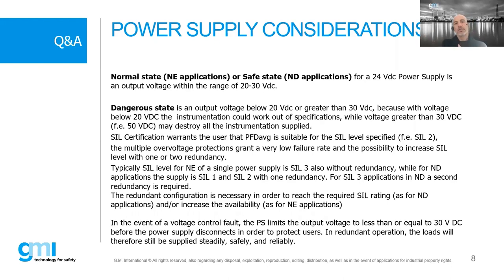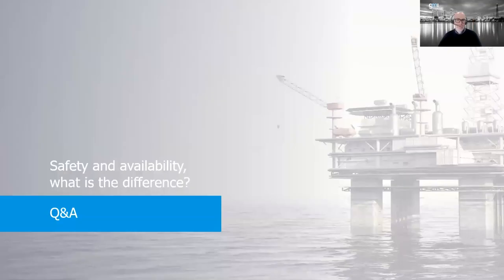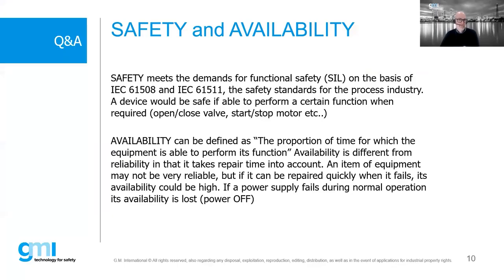If you are normally energized, which is the most common application, the redundancy grants the availability. It grants the same SIL level, always SIL3, but it grants more availability in case of fault. Okay, thank you, Andrea. And in the concept of the safety power supply, the availability is, of course, very important. What is the difference between safety and availability? So, SIL means safety, it does not mean availability. Safety means a demand of functional safety on the basis of IEC 61508 for the manufacturer and IEC 61511 for the system integrator. So it's a standard for process safety.